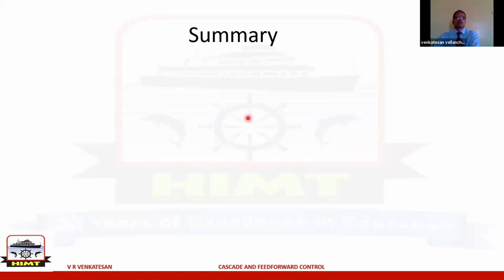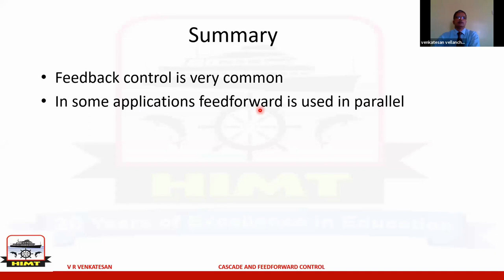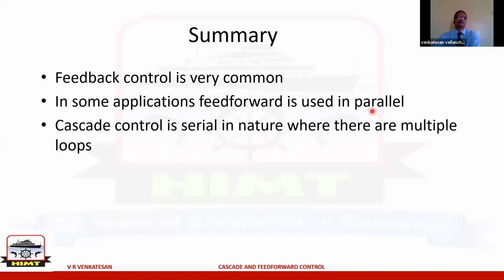To summarize: feedback control is very common and always error-based — deviation takes place and then correction occurs. Feed forward is not based on error; it is based on disturbances, which can be a load factor or changes on the input side of a process. In some applications they can be used in parallel. Cascade control is serial in nature with multiple loops.